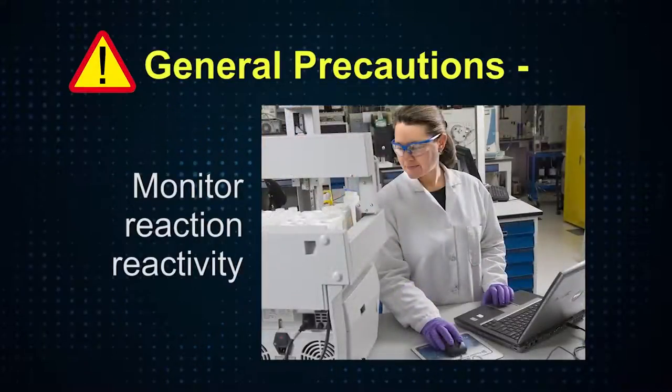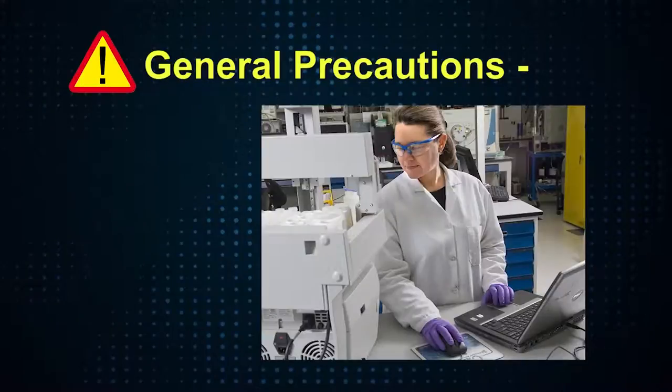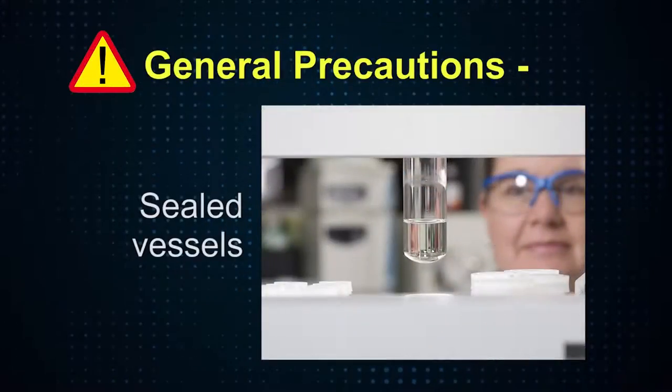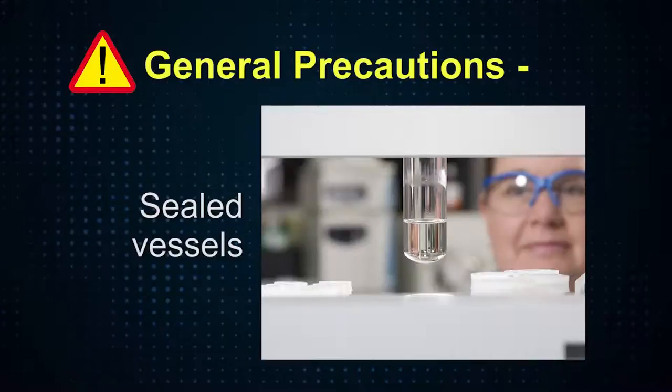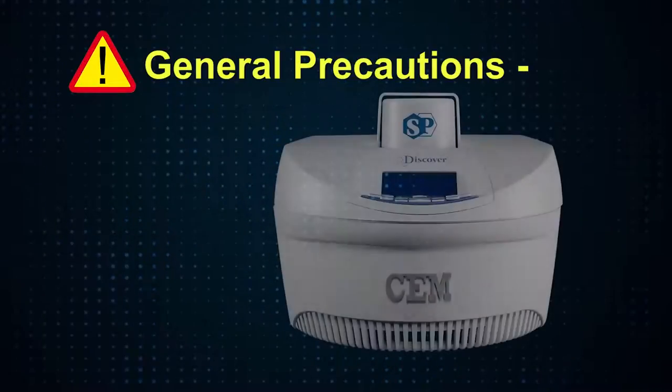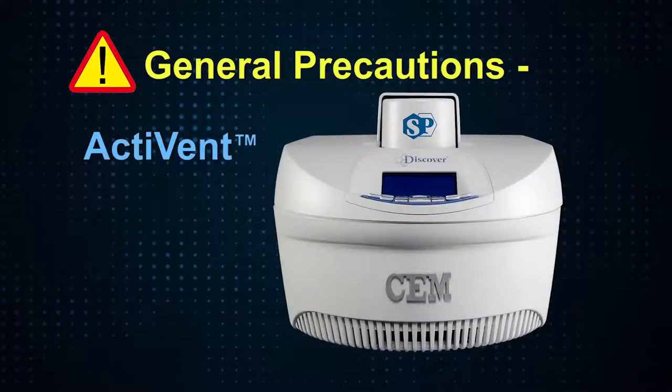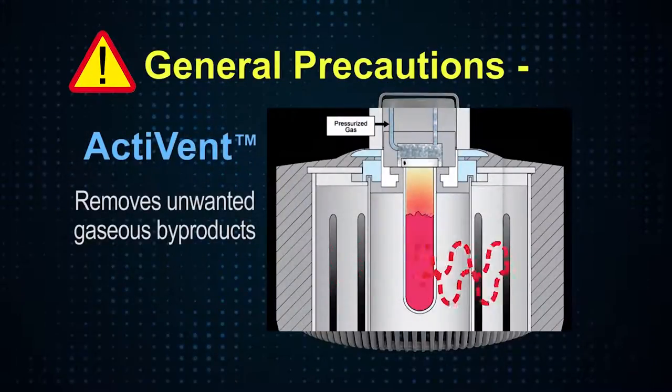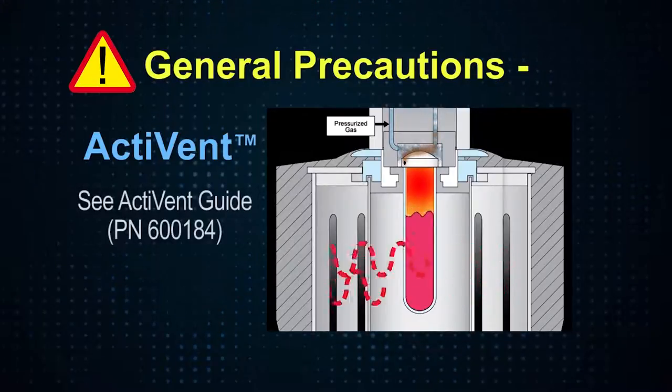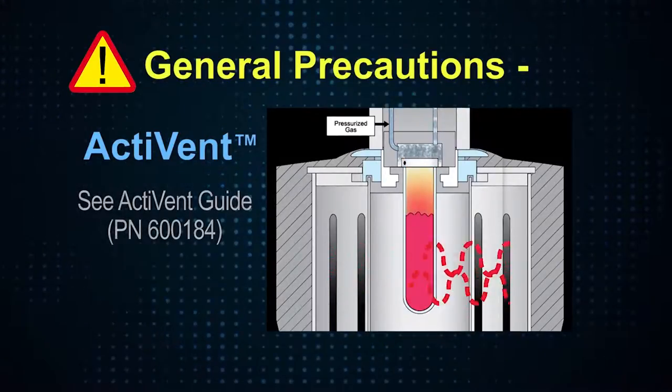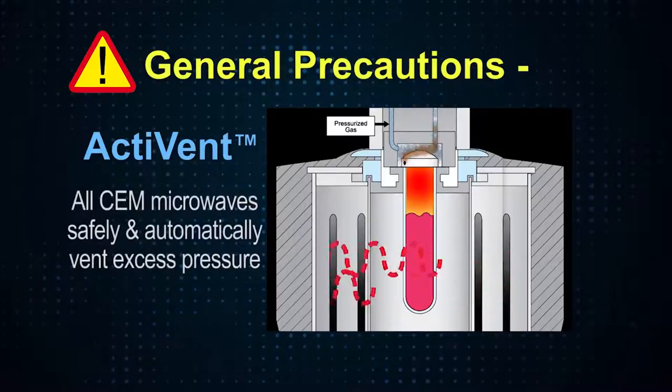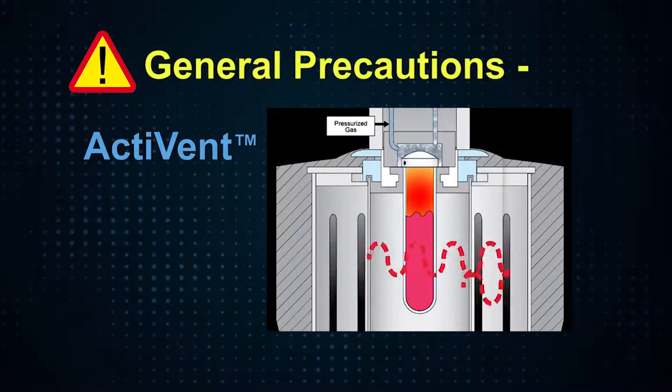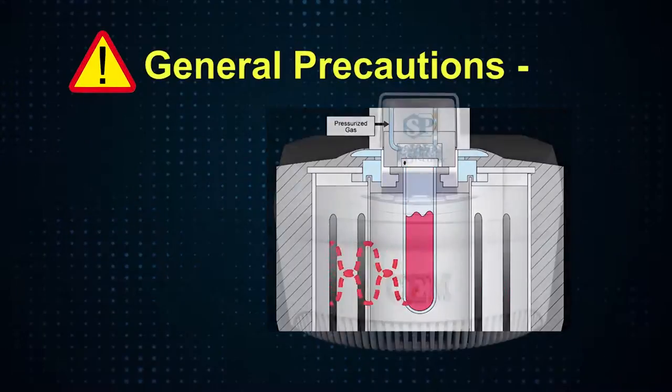Since microwave reactions are performed in sealed vessels, it's also important to be mindful of any gaseous byproducts generated during a reaction. The Discover SP features CEM's patented Activent pressure device which is capable of removing unwanted gaseous byproducts with user-defined settings. See the Discover Activent guide for instructions on programming in-situ venting. All CEM microwaves will safely and automatically vent excess pressure but chemists need to be aware of their chemistry.